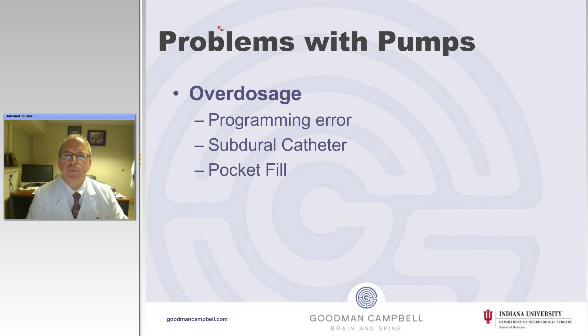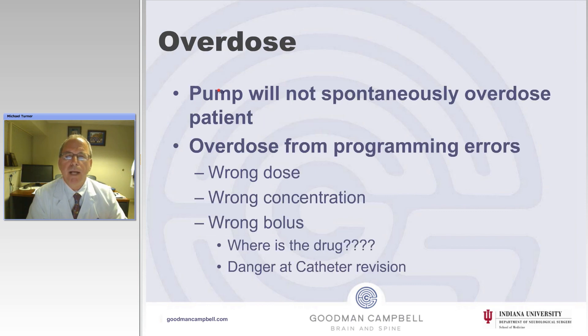Let's talk about problems with pumps. The first problem is overdosage. Overdose can come as a programming error, a subdural catheter, or a thing called pocket fill. It's very important to understand that the pump will not and has never spontaneously overdosed the patient. It is designed to internally check the flow rate virtually continuously and shuts the system down if there is an error in flow rate.